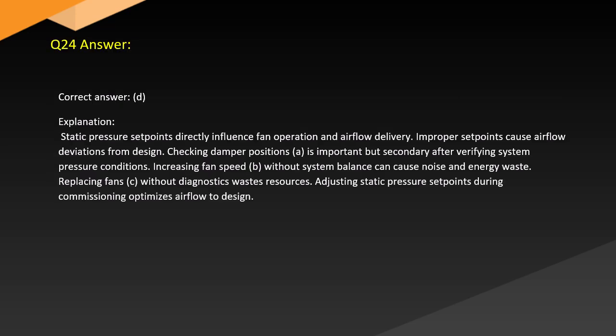Answer. Correct answer: D. Explanation. Static pressure setpoints directly influence fan operation and airflow delivery. Improper setpoints cause airflow deviations from design. Checking damper positions (A) is important but secondary after verifying system pressure conditions. Increasing fan speed (B) without system balance can cause noise and energy waste. Replacing fans (C) without diagnostics wastes resources. Adjusting static pressure setpoints during commissioning optimizes airflow to design.